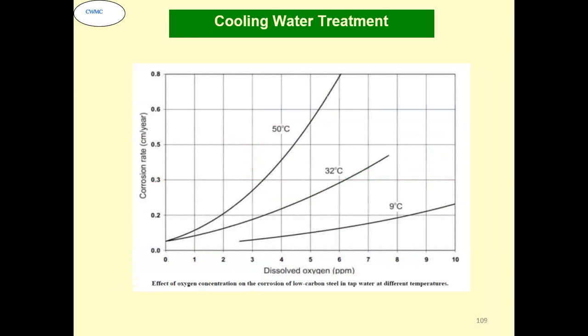Now, in general, the corrosion rate in cooling water increases to about double with every 10 degree centigrade rise in temperature. And for the normal cooling water application, the line that you see at 50 degrees, there is suddenly a peak of corrosion. That is the normal operating area of the heat exchanger, about 49 to 50 degrees, and that is where the maximum corrosion is seen.